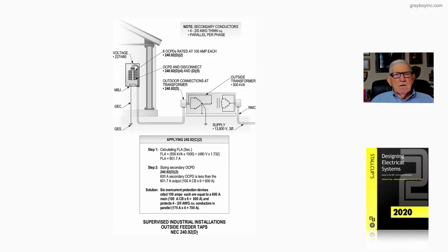Now, for example, if you review the note, it says secondary conductors. We have 4 2-aughts in parallel per phase. And of course, table 310.16 lists those 2-aught conductors in a 75-degree column at 175 amps. So 4 times that would be around 700.